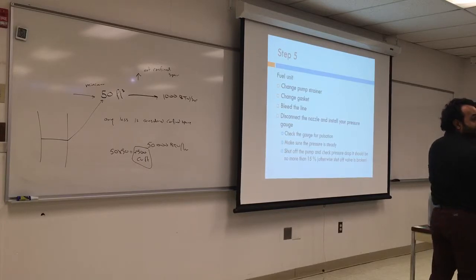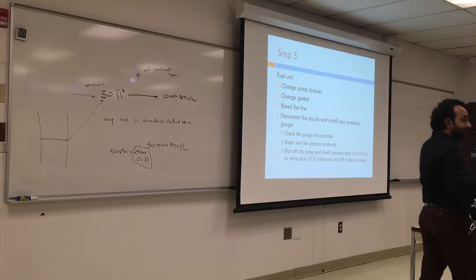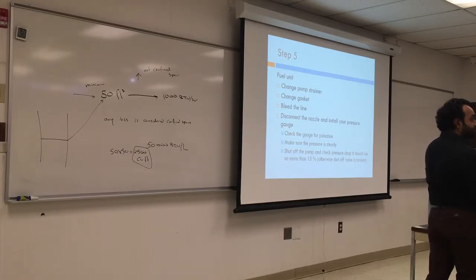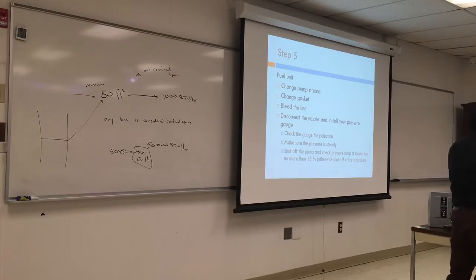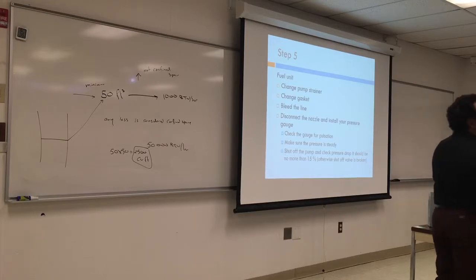I've seen some people where the boiler is in a very tight location, so they just open the line and put a pan underneath. That's not a good idea. Make sure you always connect the hose. That's why there's a knob in here. Put a hose, even if it goes up, there's enough pressure to pull it out. Do not put just a can underneath and try to bleed it that way. It will splash. It's a lot of pressure. So have the proper tool.